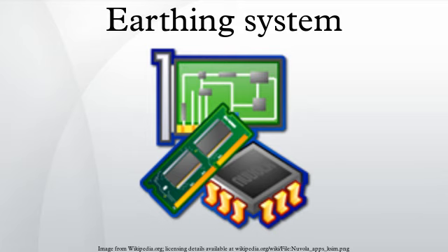In the absence of any insulation fault in the consumer device, the equation IL1 + IL2 + IL3 + IN = 0 holds, and an RCD can disconnect the supply as soon as this sum reaches a threshold. An insulation fault between either L or N and PE will trigger an RCD with high probability. In IT and TN-C networks, residual current devices are far less likely to detect an insulation fault. In a TN-C system, they would also be very vulnerable to unwanted triggering from contact between earth conductors of circuits on different RCDs or with real ground, thus making their use impracticable.